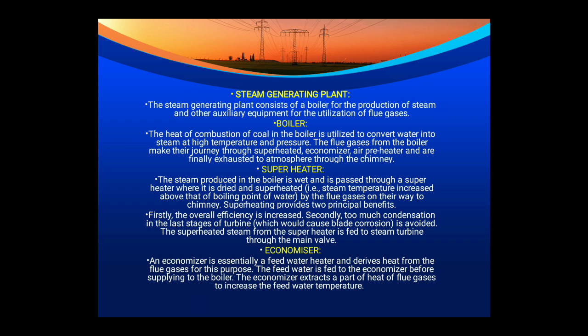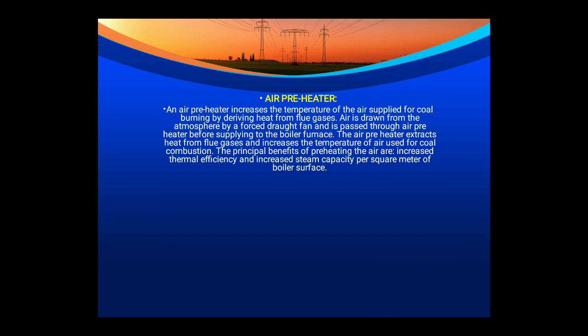An economizer is essentially a feed water heater that derives heat from the flue gases. Feed water is fed to the economizer before supplying to the boiler; the economizer extracts part of the heat from flue gas to increase feed water temperature and boiler efficiency. An air preheater increases the temperature of air supplied for coal burning. Air is drawn from the atmosphere by a forced draft fan and passes through the air preheater before being supplied to the boiler furnace. The principal benefits of preheating the air are increased thermal efficiency and increased steam capacity per square meter of boiler surface.